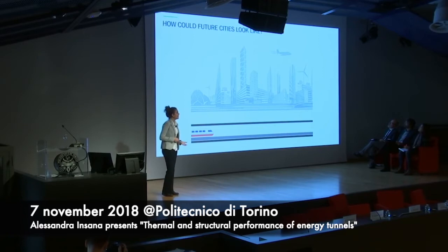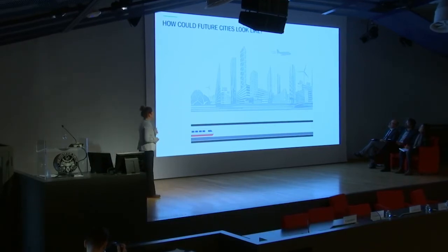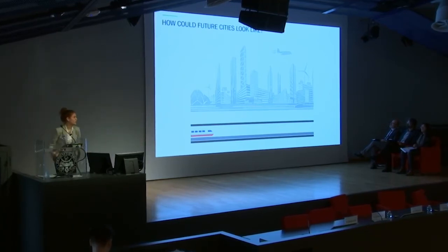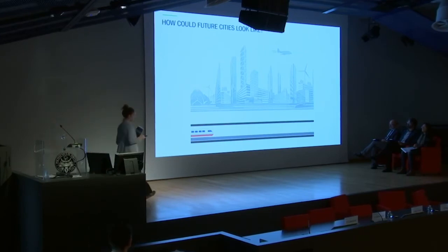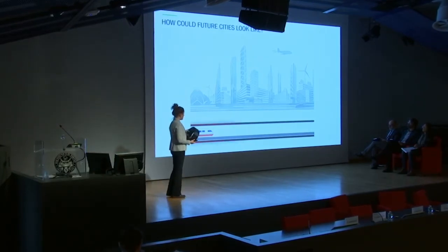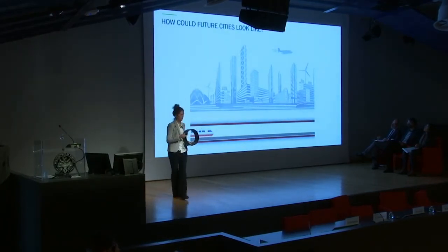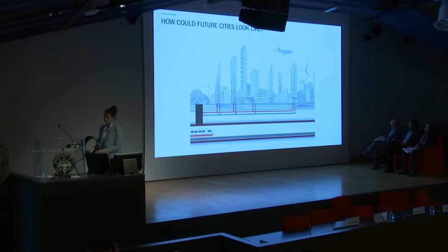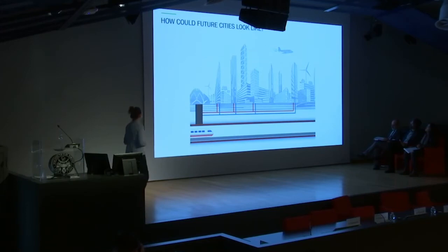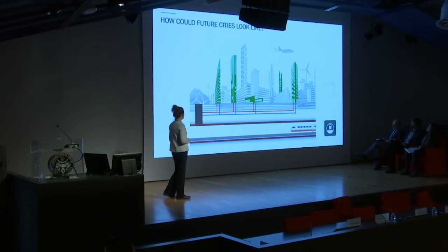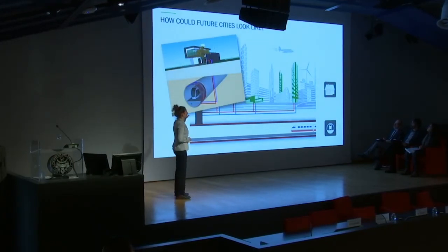Now, in the underground of a city, we have, for example, metro tunnels. And tunnels can be turned into a huge radiator crossing the whole city, turning them into a heat exchanger, as we can see in this small-scale prototype here, by embedding a circuit of pipes into the concrete elements that support the ring. So this circuit can then be connected to the heating and cooling systems of the buildings above, so that they can benefit from a green, renewable, and clean source of energy. And this would be the final system that we achieve.